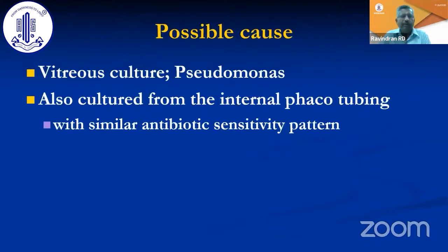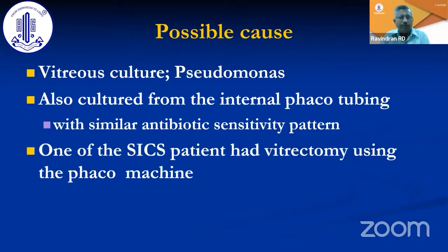And the possible cause: we were able to culture the same Pseudomonas which we cultured from the vitreous also from the internal phaco tubing, with a similar antibiotic sensitivity pattern, which we feel could be the cause. Whatever the contamination, this happened a long time back, like 15 years back, when this used to be a problem.